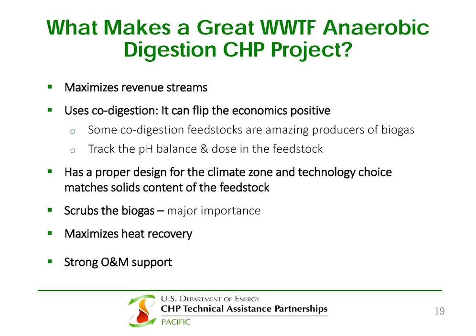As far as design lessons: make sure all parts of the system are properly sized. Don't oversize the genset compared to biogas supply—biogas, not thermal load or electric load, governs sizing, so you've got to know your biogas. Natural gas can supplement biogas; it stabilizes gas flow to the genset, helps match genset size to critical load requirements, and can support digester temperature requirements.